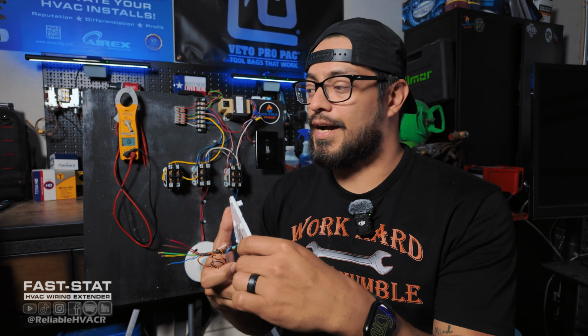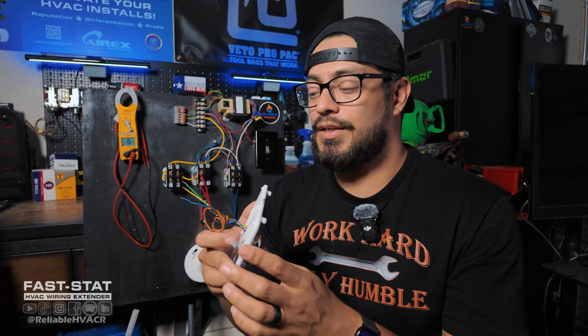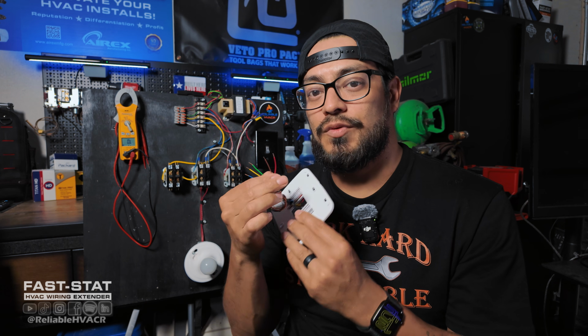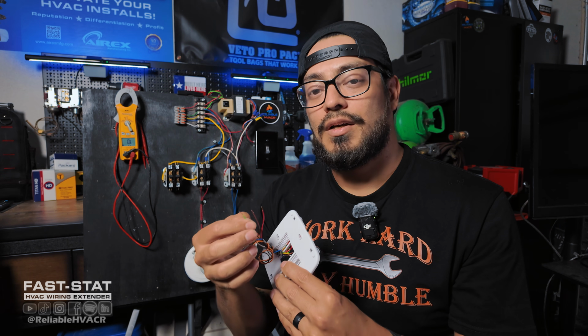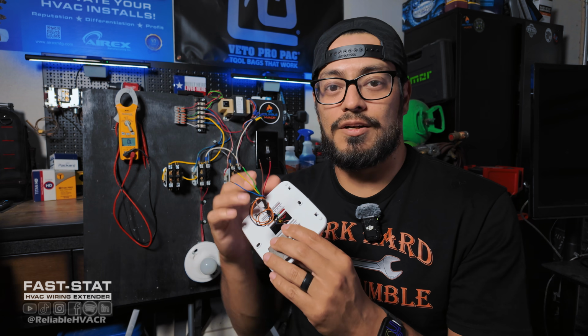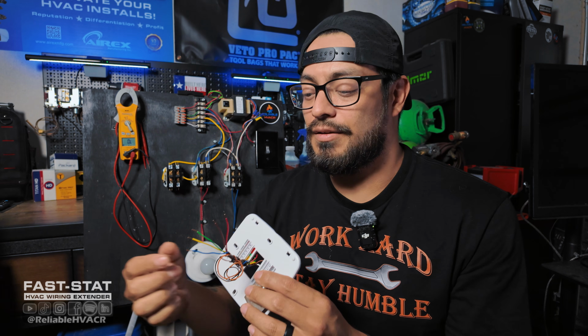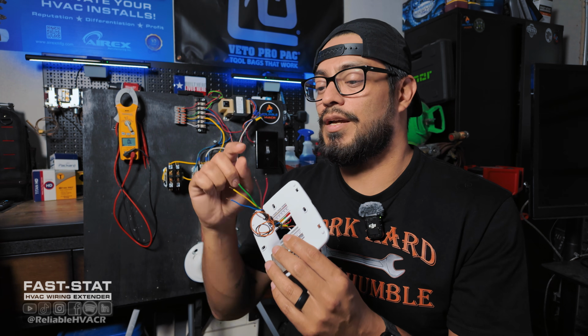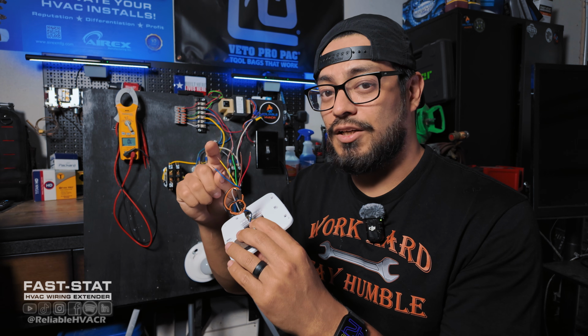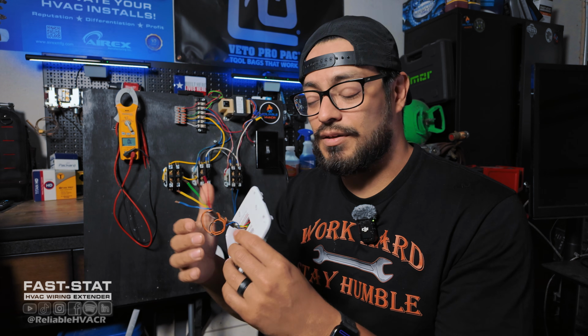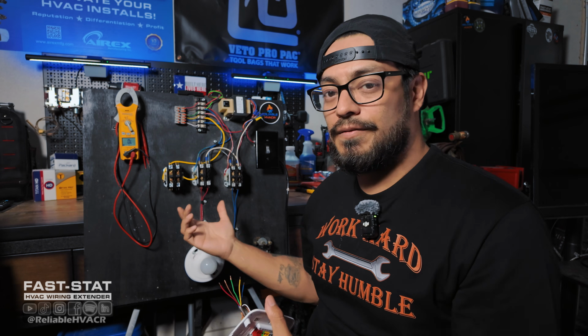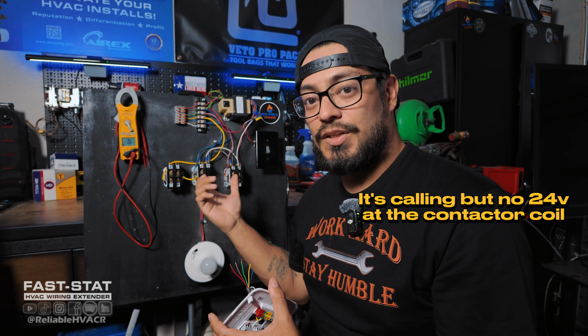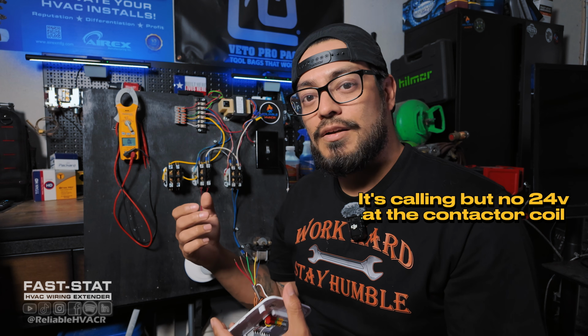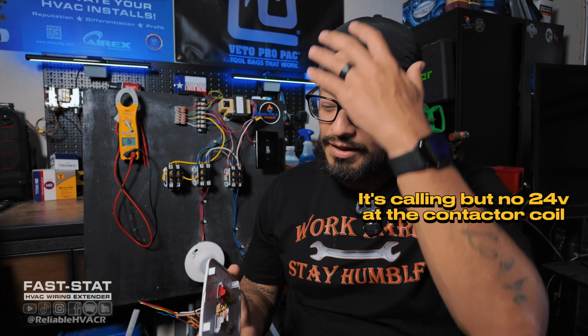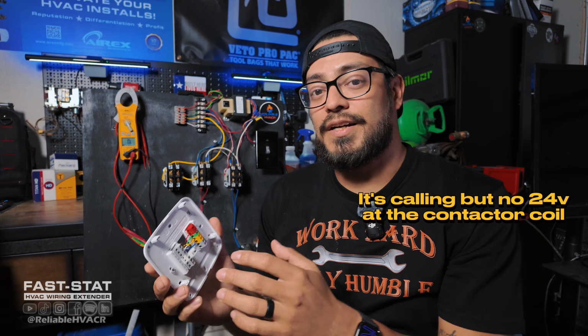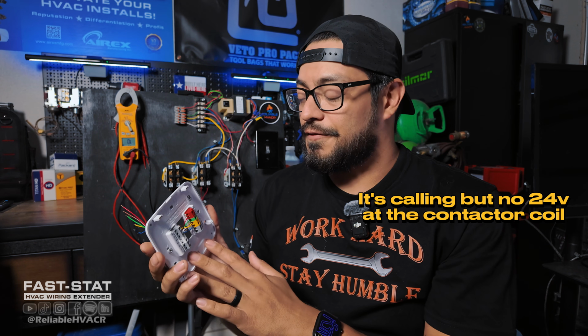Basically, like I said, isolate the thermostat by taking off the faceplate. Isolate the other end by removing it off the board or terminal connections, or wherever it ends to, right? And make sure you check it that way. Now, if your wiring is okay and you're still not getting a call, like it is calling but the contactor never pulls in, obviously wait for that 5-minute delay, or whatever delay the manufacturer specifies. But there's a few other things you can do.